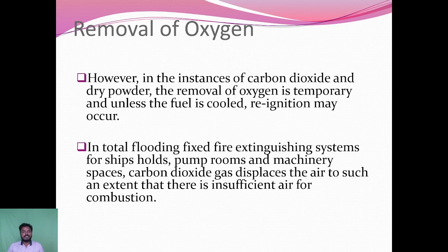However, with carbon dioxide and dry powder, the removal of oxygen is temporary unless the fuel is cooled. Reignitions may occur. In total flooding, firefighting extinguishers should be in the ship hold, pump rooms and machinery space. Carbon dioxide gas displaces the air to such an extent that there is insufficient air for combustion.